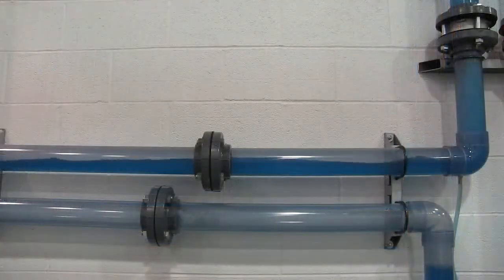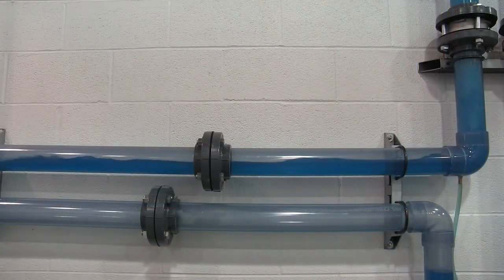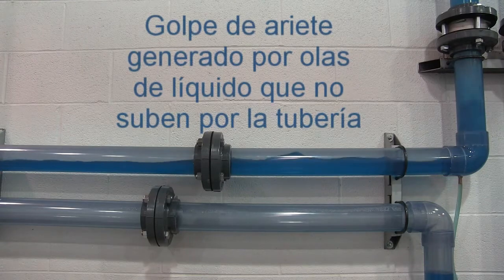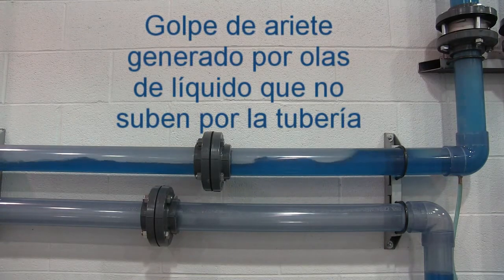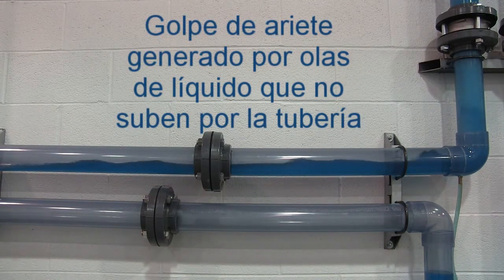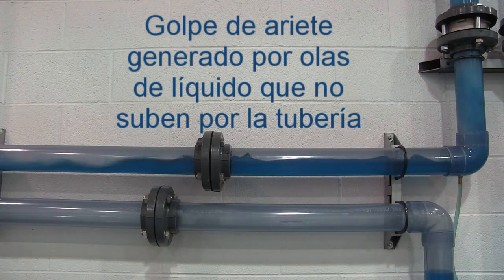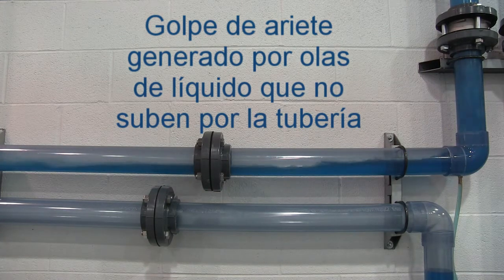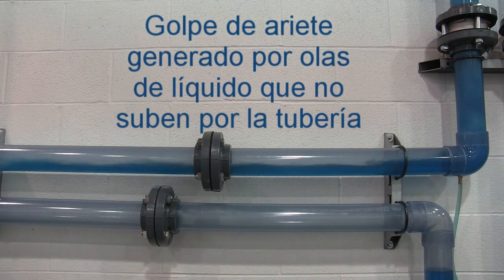Elevation changes in two-phase condensate return lines are especially prone to creating condensate backup, which can lead to damaging water hammer. The damage can be especially severe due to the magnitude of condensate mass present as the pipe size increases in diameter.